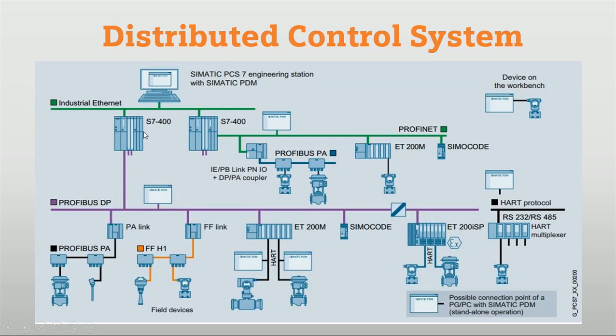From the automation station — which is the master control or dedicated control — we have connected a coupler with Profibus DP, and from the coupler we have connected field devices with active field transmitters or active field distributors. Different communication protocols are used, like ASI interface, Profibus DP, Profibus PA, distributed IO systems, and Simocode kits. Throughout the network we have different communication protocols and networking devices, all connected with the main automation station. With the automation station we can also connect HMI or operating stations for monitoring and controlling the process.